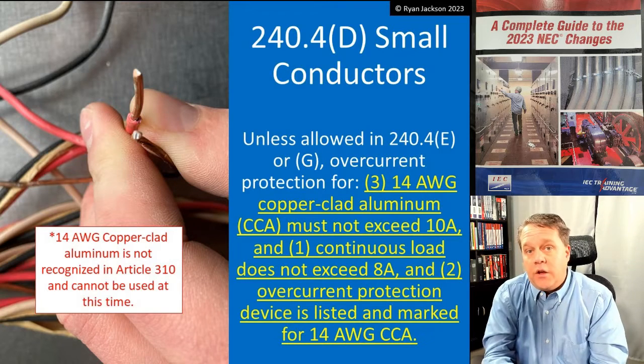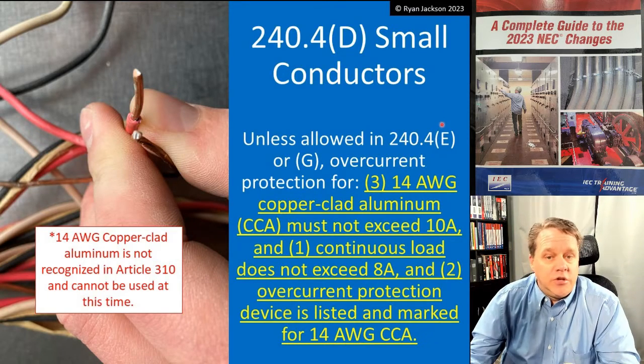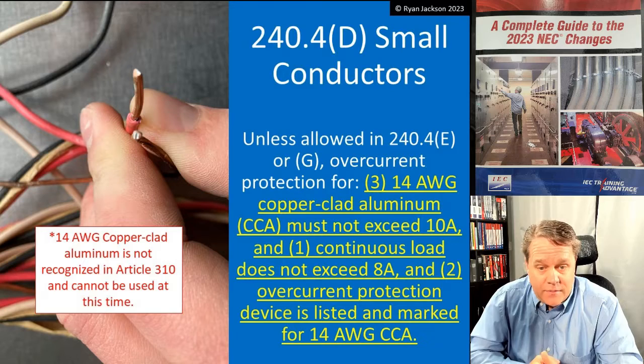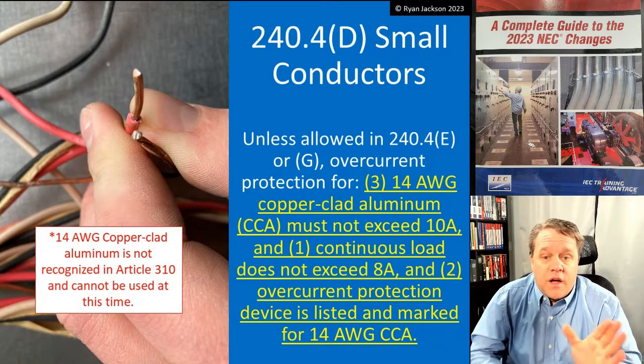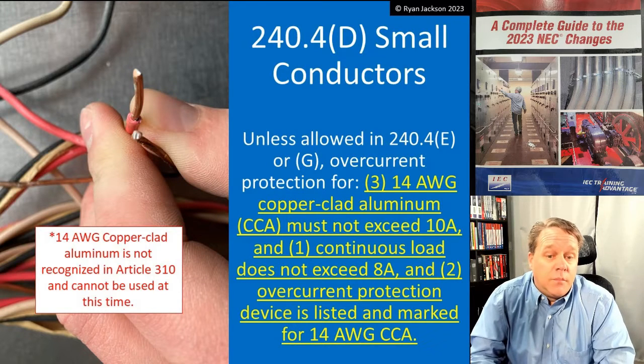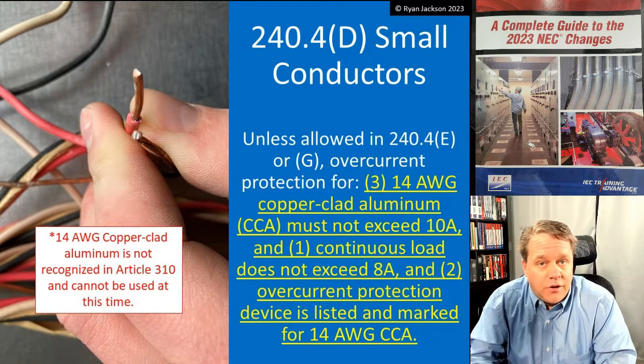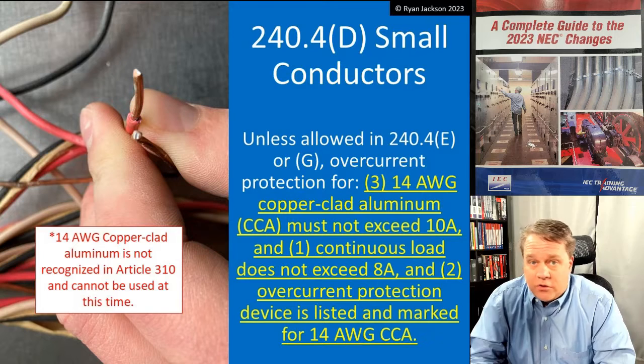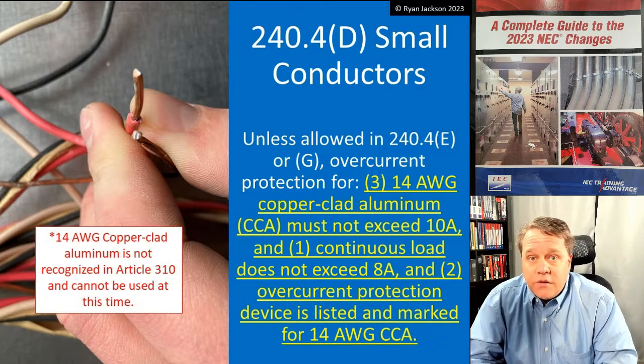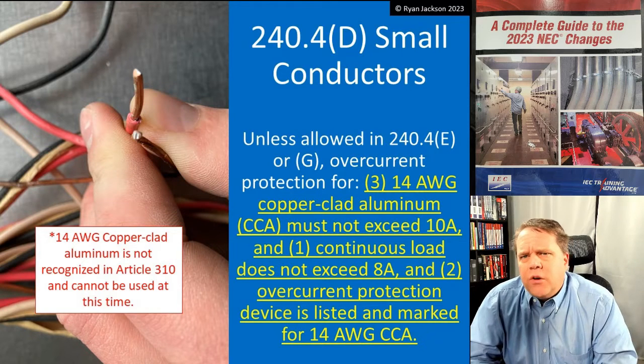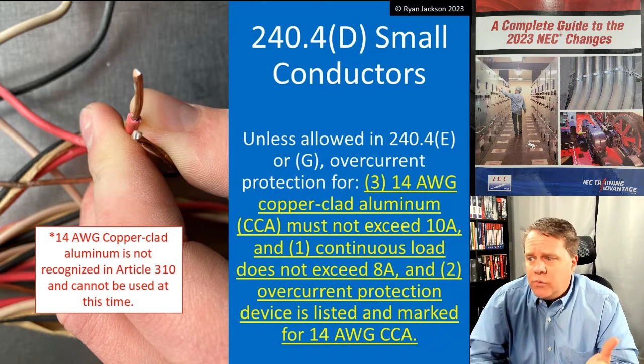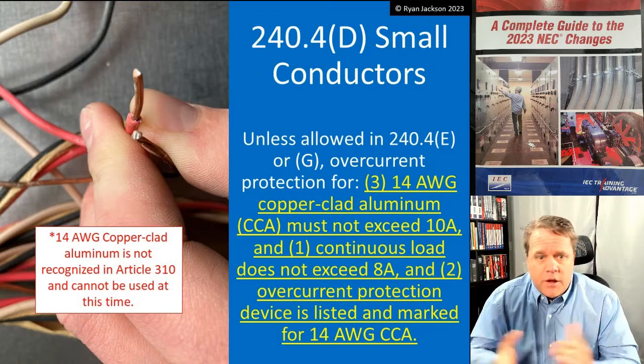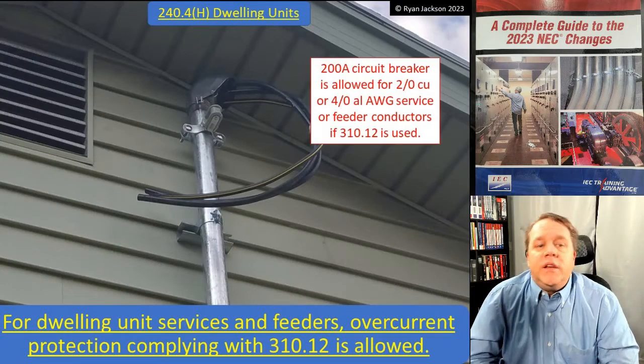Unless allowed in (E) or (G), overcurrent protection for 14 AWG copper-clad aluminum must not exceed 10 amps, the continuous load must not exceed 8 amps, and the overcurrent protection device must be listed and marked for use with 14 AWG copper-clad aluminum. This conductor type isn't currently being manufactured because it can't be installed yet, but if it's ever allowed — perhaps in the 2029 NEC — we'll be ready to install and protect it.